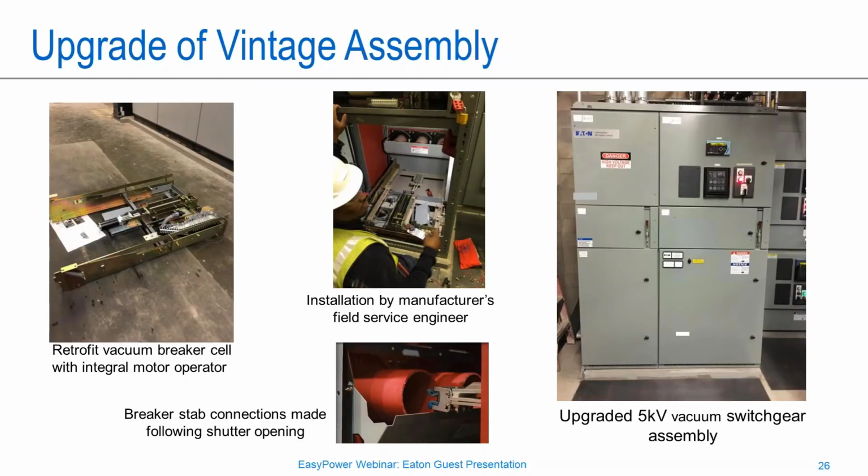There's quite a bit of sophistication in these cell parts, in that there are individual limit switches, so you know where the breaker position is, connected, disconnected, or test position, so you know where the breaker is while it's being racked on or off of the bus. There's also a torque sensing functionality, so if something gets jammed or stuck during the racking, then an alarm goes off and the racking is ceased.